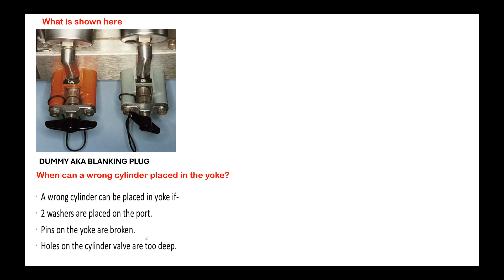And when can a wrong cylinder be placed in the yoke? Is it possible to fit an oxygen cylinder in a nitrous oxide yoke? A wrong cylinder can be placed forcefully in two ways. If two washers are placed on the port, instead of one Bodok seal, you put two washers, then still you can tighten and fix it. Or if the pins in the yoke are broken and the holes in the cylinder valve are too deep, that also can allow the cylinder to be fixed in the wrong place.